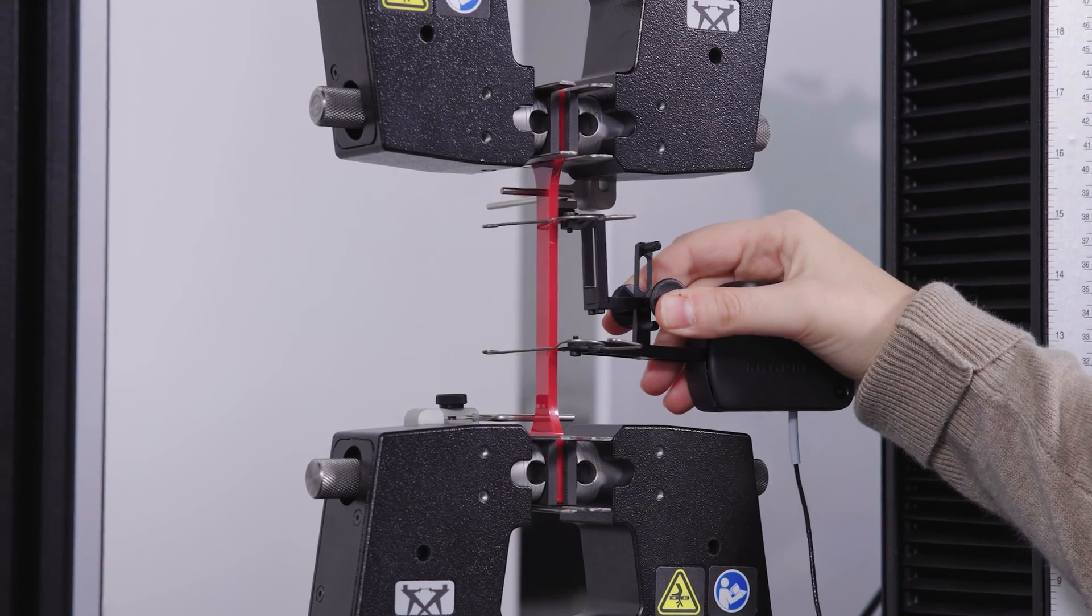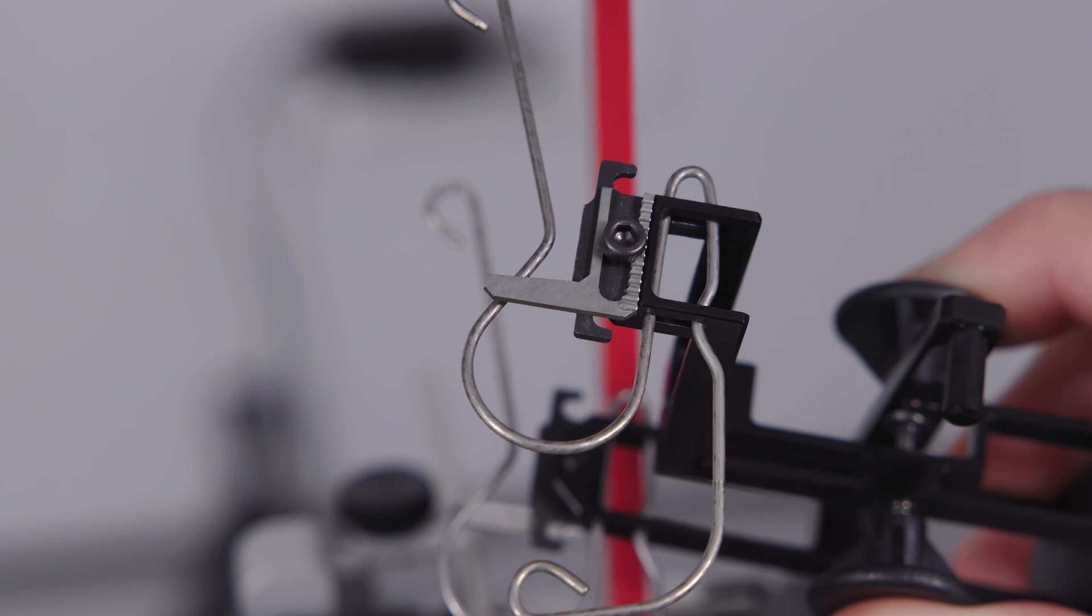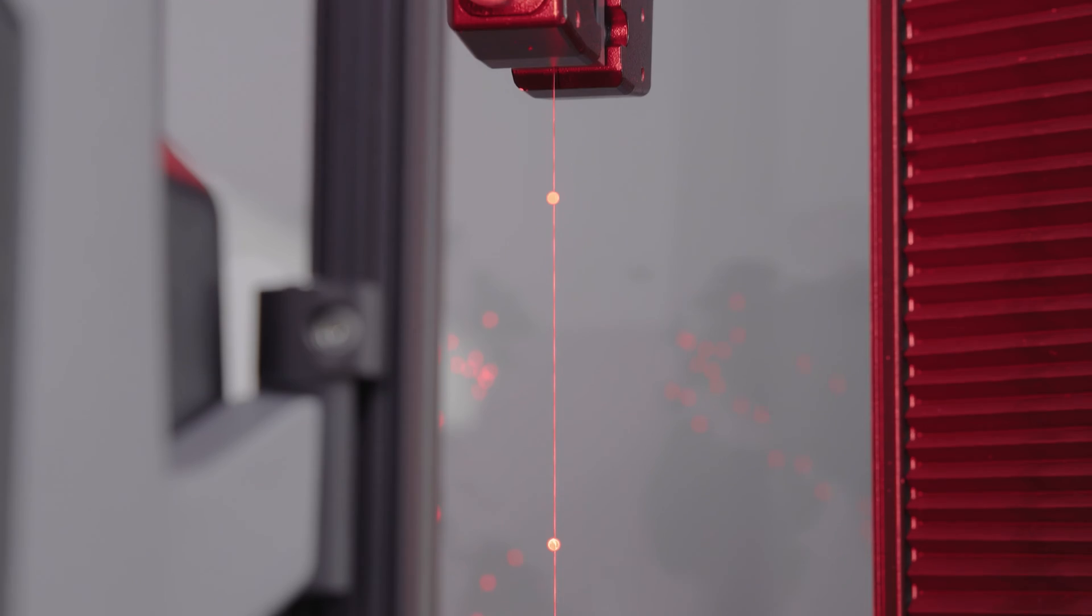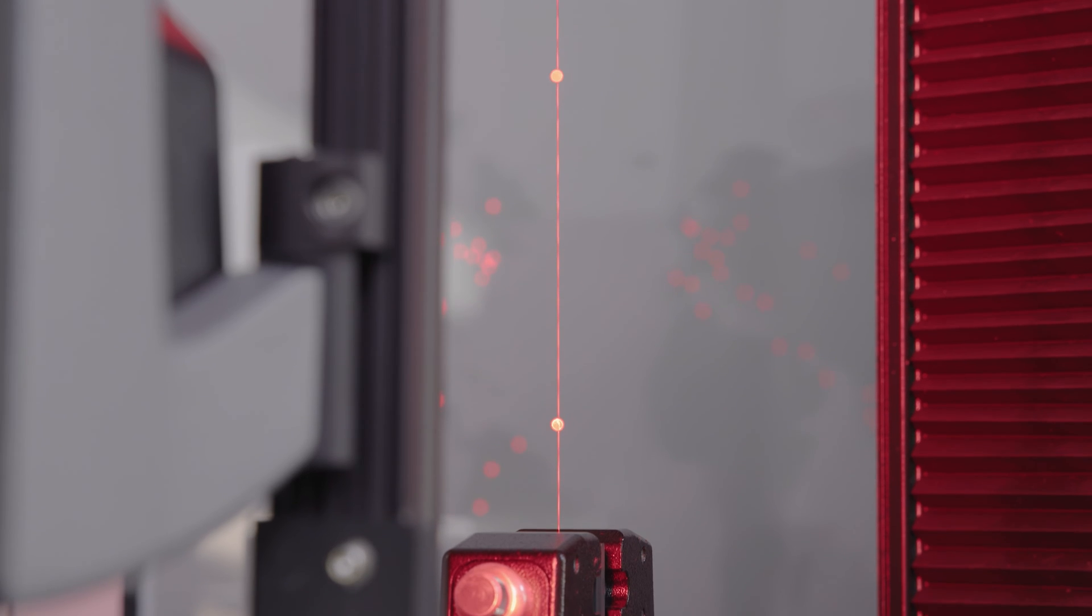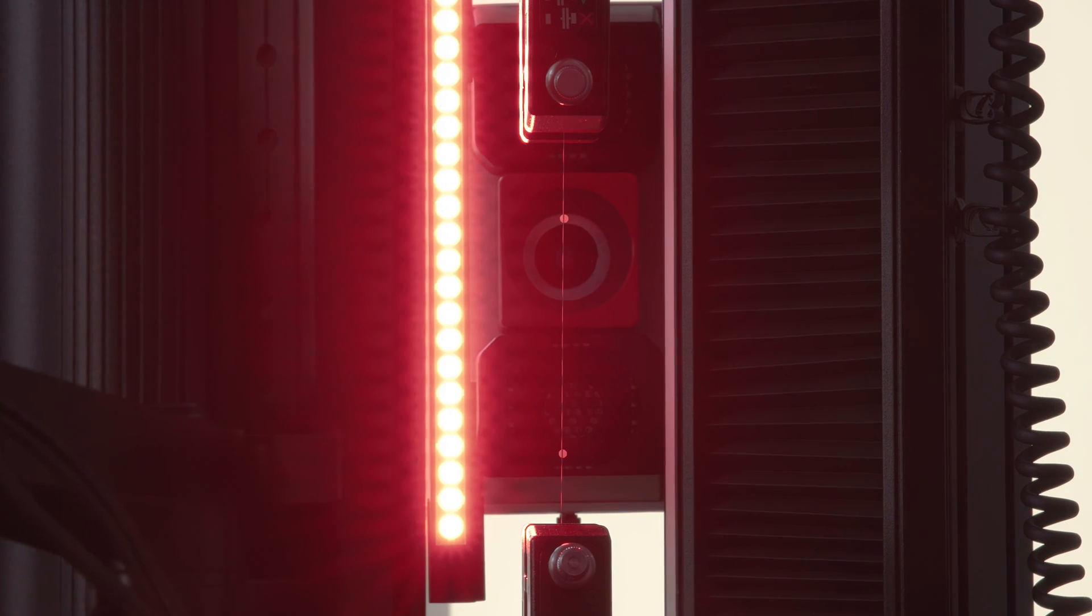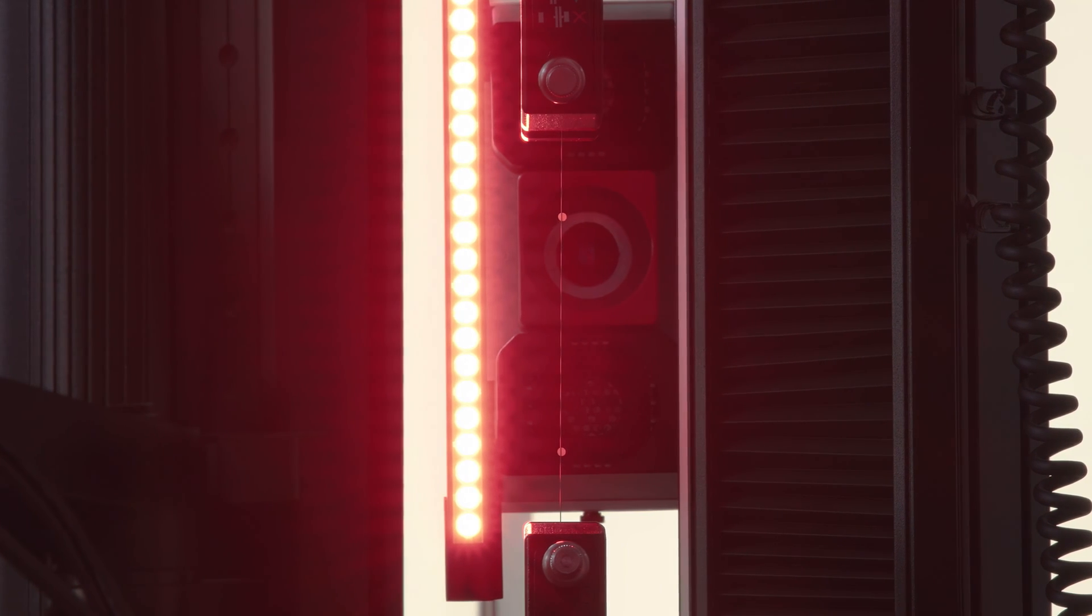Though contacting extensometers are suitable for many applications, their knife edges can compromise thin or fragile specimens. For these materials, non-contacting video extensometers are preferred.